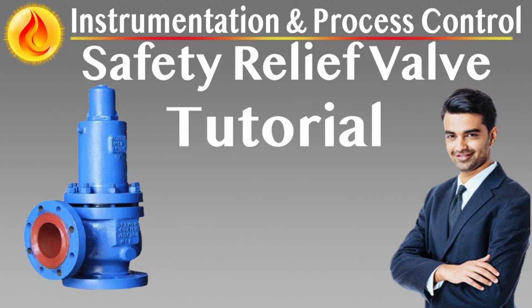Design limitations and cautions. These valves are not suitable for systems where multiple relief valves may open simultaneously, generating variable back pressure that could prevent a valve from reaching full lift, or cause delayed or failed opening in high-pressure scenarios. For systems with potential relief valve interaction or shared discharge headers, use of balance-type valves or conservative pressure settings should be evaluated. Closed bonnet designs are mandatory when discharging into closed systems to prevent process fluid from entering the spring housing.